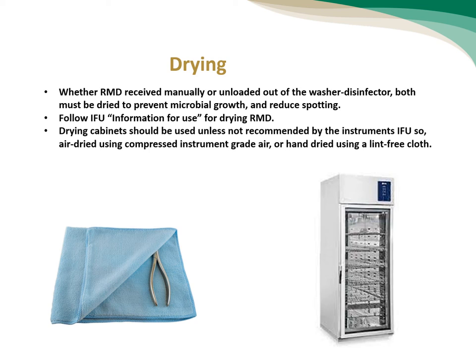Drying cabinet should be used unless not recommended by the instrument IFU. So air dried using compressed instrument grade air, or the medical air you have in your department, or hand dried using a lint-free cloth. It will not leave any debris or textile on the instrument. So we have to use the correct lint-free cloth. That's it.